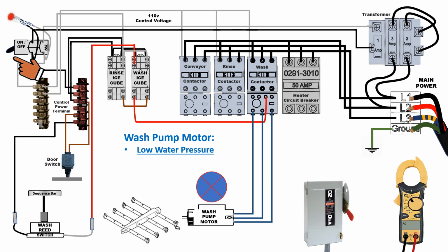First, we turn off the master on-off switch. Next, we shut off main power by throwing the disconnect or turning off a circuit breaker. Always ensure that you lock out tag out. Ensure the machine is safe to work on so no one can turn it on while you're working. Next, using a multimeter, set to AC voltage, one meter lead to ground. We'll be testing L1, L2, and L3, all main leads coming in, to ensure we have no power coming into the machine.